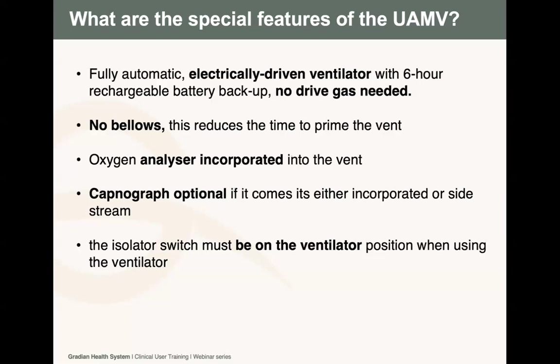And during ventilation, still work as for the previous, the isolator switch must be on the ventilator side. If you forget, then you will have a challenge, you might not get to deliver what you need, and then the machine will be giving you alarms, high pressure or low pressure, and then you have a noisy machine during your anesthesia. Next slide, please.